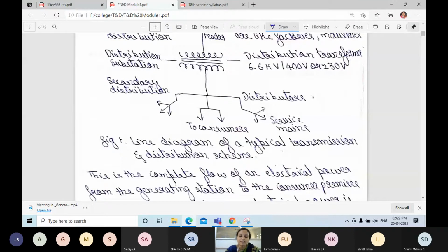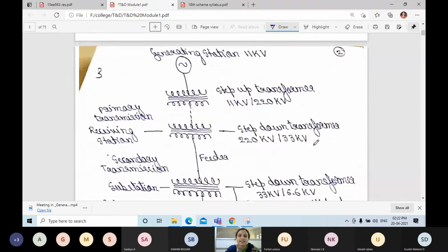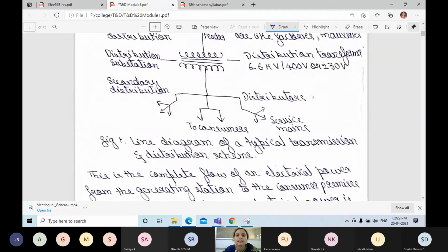Starting from the generating station at 11 kV, we step up to 220 kV, and from 220 kV we again step down to 66 kV or 33 kV. From 33 kV we go to 6.6 kV, and from 6.6 kV we come down to 400 or 230 volts. Or we can take 6.6 kV to 3.3 kV, and from that reduce to 400 or 230. This is the line diagram of a typical transmission and distribution scheme. They have asked this many times.